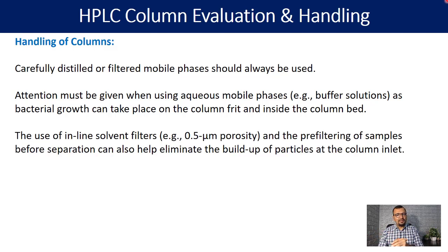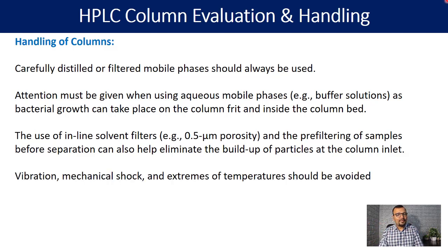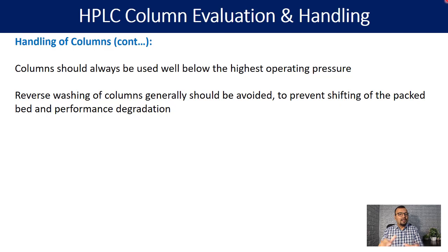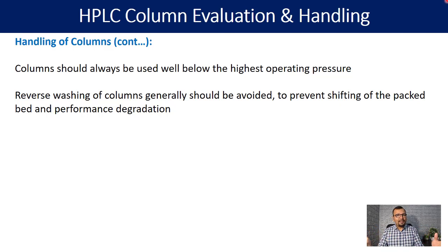The use of inline solvent filters — like 0.5 micron porosity — and pre-filtration of the sample before analysis can always help protect your column's health. Vibration, mechanical shock, and extremes of temperature should always be avoided. The column should always be used well below its highest operating pressure. Reverse washing of the column should generally be avoided to prevent shifting of the packed bed and performance degradation. Sometimes reverse flushing may seem to improve column performance for a short time, but eventually you are degrading the column performance in the longer term.